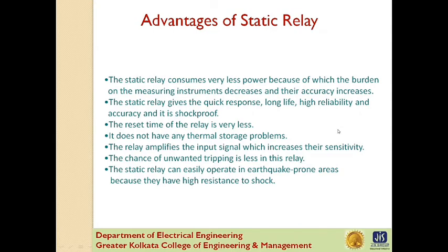Now, what are the advantages of static relay? First, the static relay consumes very little power, because of which the burden of the measuring instrument decreases and its accuracy increases. Second, the static relay gives quick response, long life, high reliability and accuracy, and it is shock proof. Third, the reset time of the relay is very less. Fourth, it does not have any thermal storage problems.